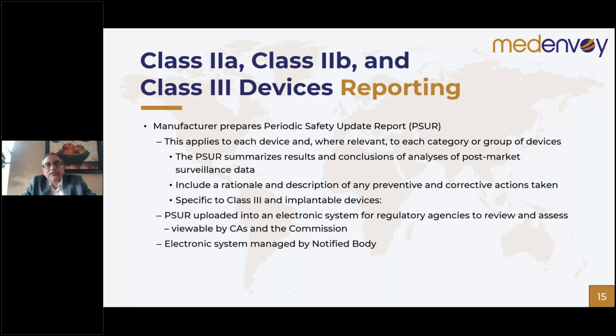A lot of notified bodies have created dedicated emails, and they expect you to submit through those dedicated emails at certain times. So there should be a defined mechanism for how you will communicate with your notified bodies. And of course, you can interact with your notified body to ensure their expectations are met. Not during the audit, by the way. It has to be done prior to the audit, because during the audit, if there is no evidence of an established mechanism to communicate, it will be a non-conformance.